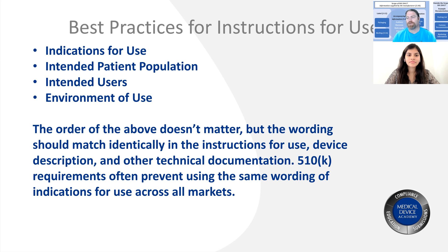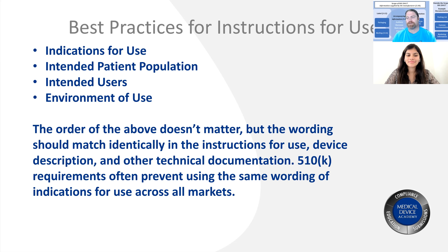You want to use the exact same wording — copy and paste that information into your device description. It is actually required to have the exact same wording in both places. This gives you the complete indication for the device or the complete intended purpose. We have a template for a device description created using the FDA guidance, the FDA RTA checklist, and the European checklist for what they want in a technical file. Just use those four headings and have a concise sentence or two for each one — that's best practice for writing your instructions for use.